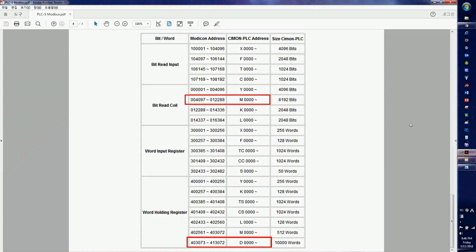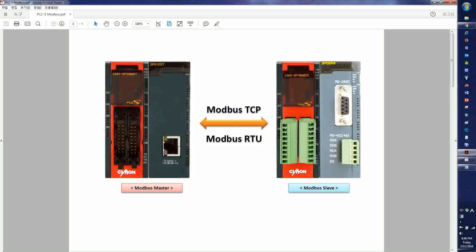For the last one, I'm going to show you the Modbus TCP, which is a lot simpler and easier than Modbus RTU. The Modbus TCP master must be the SP01ET module — the Ethernet module. The CPU type cannot be Modbus master; this one should only be Modbus TCP master.